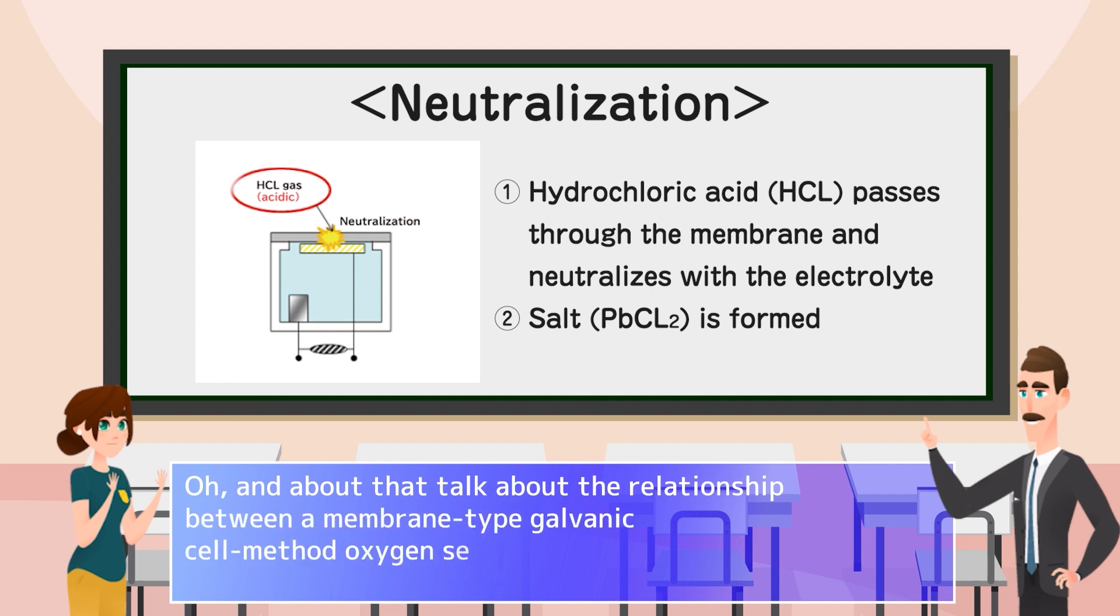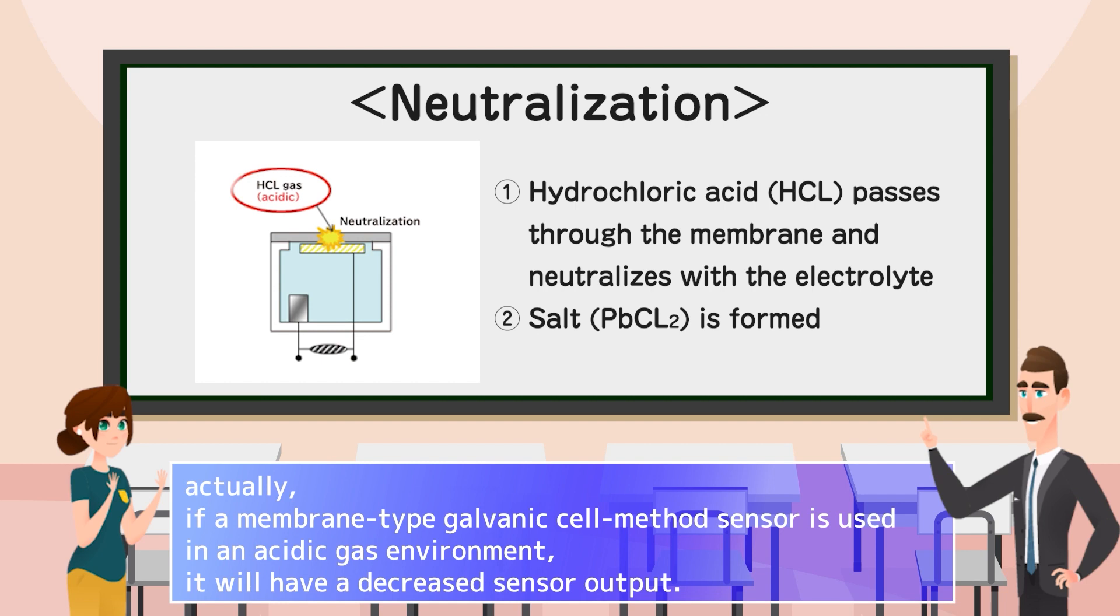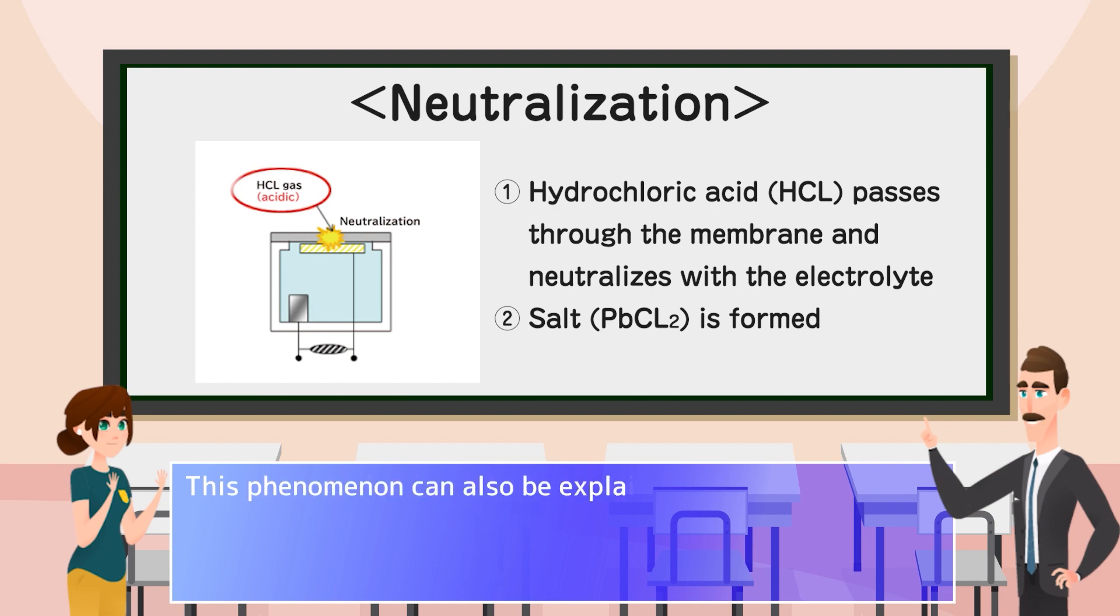Oh, and about that talk about the relationship between a membrane-type galvanic cell method oxygen sensor and acidic gas you said you heard recently. Actually, if a membrane-type galvanic cell method sensor is used in an acidic gas environment, it will have a decreased sensor output. This phenomenon can also be explained through neutralization.